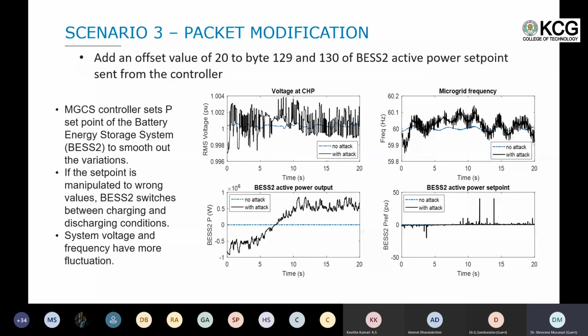The battery set point is manipulated, and the battery starts charging, discharging, charging, discharging, and a lot of charge-discharge cycles happen. The blue one shows when there is no attack: everything was good, the frequency was good, the voltages were good, and fundamentally the battery active power was good. But when an offset was added, it starts discharging more, and fundamentally it has more oscillations on the frequency. Now, depending on how much things get added up, it can cause a catastrophic scenario in terms of the tripping of the relays and so on.